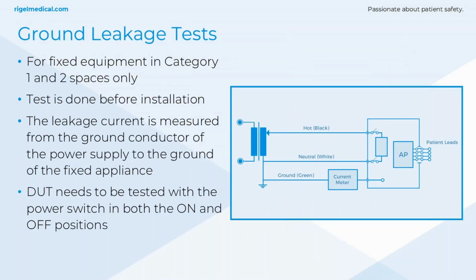So the first test I want to talk about is ground leakage. Now, it's not going to be performed as often as your other leakage tests. In the latest revision of NFPA 99, it's only specified for fixed equipment in category 1 and 2 spaces before you install that equipment. But for those still using 2012, this is obviously a test that's still included amongst most users.